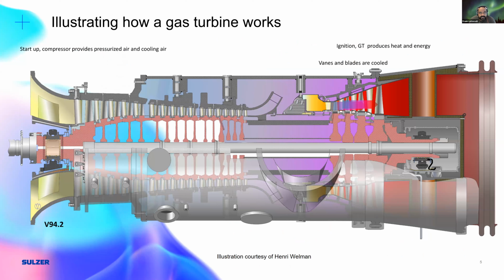So this is a cross-section of what a gas turbine looks like, courtesy of Henri Welman, who was able to provide me with this drawing. You see that you have your compressor here, and your compressor is connected to the turbine. This is for the V94.2. For those who don't know what the V94.2 looks like, you have two silo combustors on each side of the rotor, and then you have a compressor and then a turbine. So literally there is a startup where the compressor provides pressurized air and cooling air. The cooling air is required for the turbine blades and the vanes. Then you have the ignition that produces the heat and energy in the combustor, and then the vanes and blades that are cooled to make sure that they do not expand too much, and the heat exhausts into the boiler.